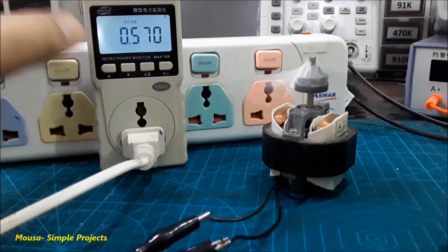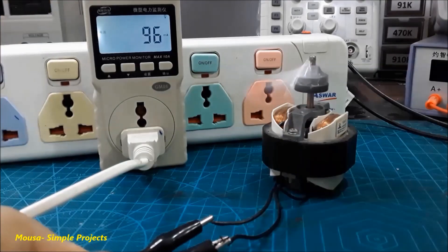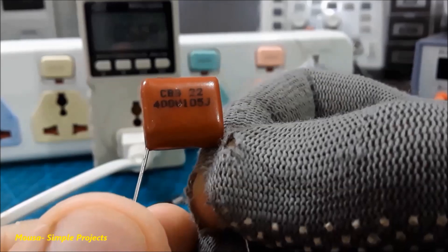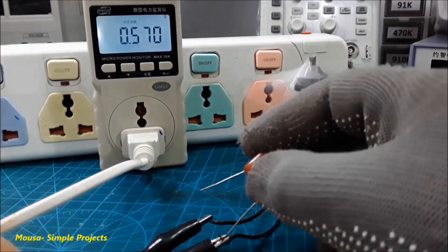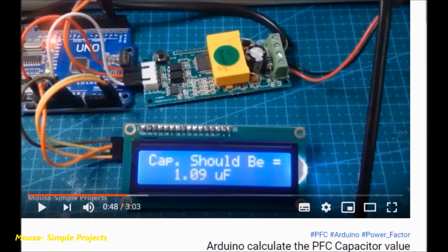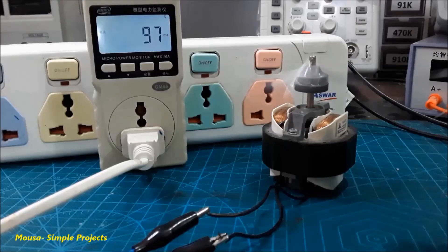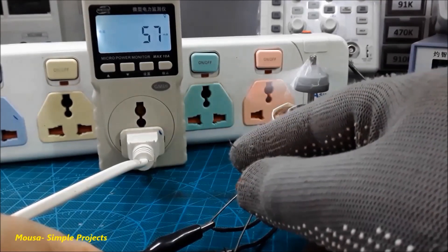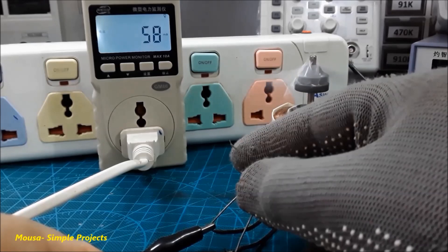Here I have this tiny 15-watt motor. The power factor of this motor is about 0.5 and its drawing current is about 96 milliamps. I can increase the power factor of this motor simply by adding a one-microfarad capacitor to it. As you can see, the current drawing of this motor drops from 97 milliamps to about 57 milliamps.